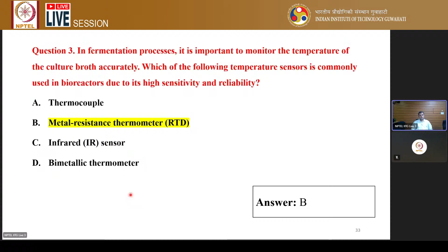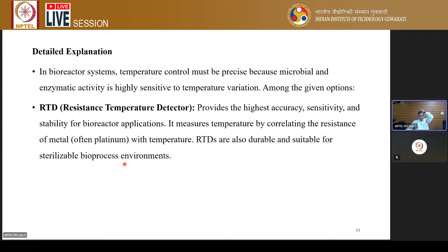Due to its high sensitivity and reliability, this is based on the metal resistance thermometer, also known as RTD. RTD provides the highest accuracy, sensitivity, and stability for bioprocess applications. It measures temperature by monitoring the resistance of a metal, typically platinum, with temperature. RTDs are also durable and suitable for sterilizable bioprocess environments, as we often need to sterilize this sensor.